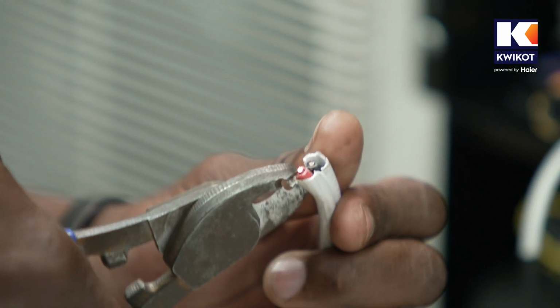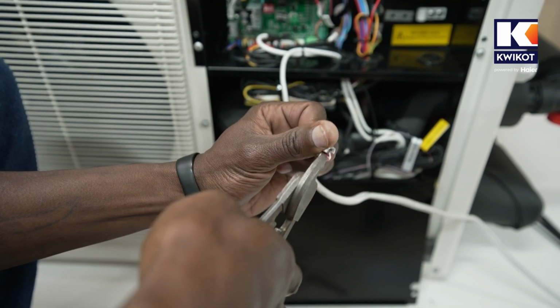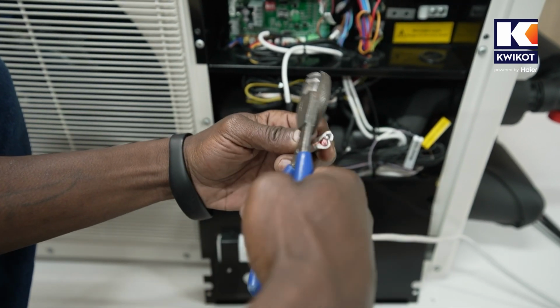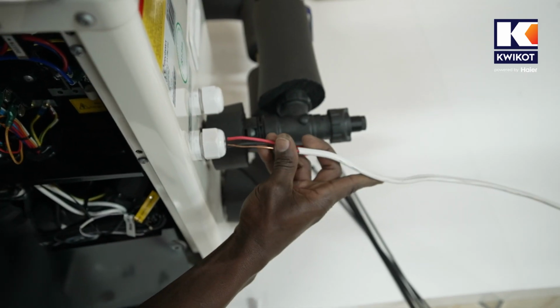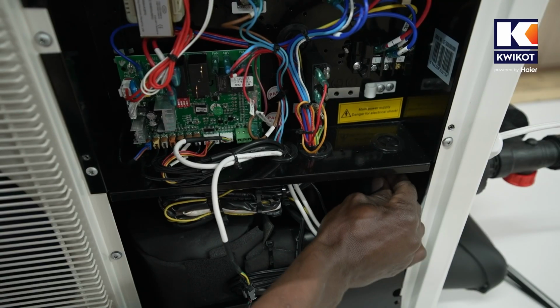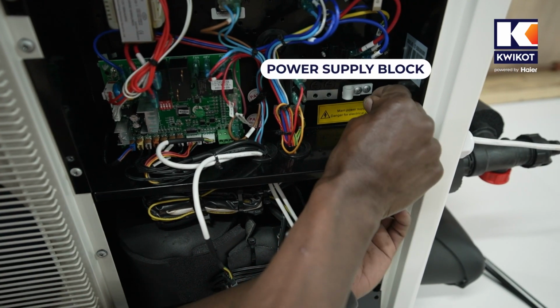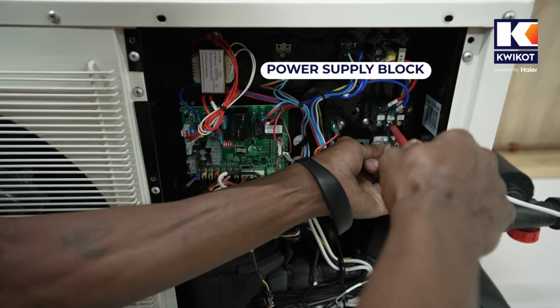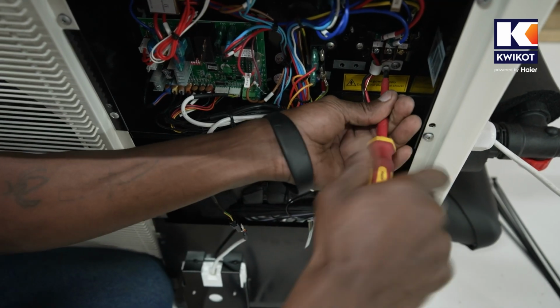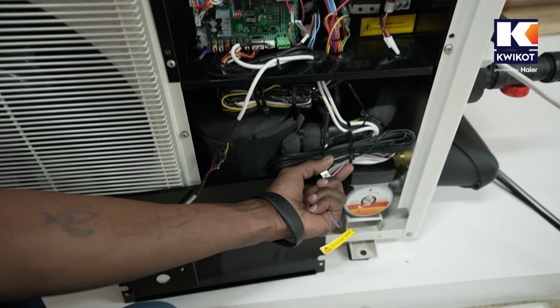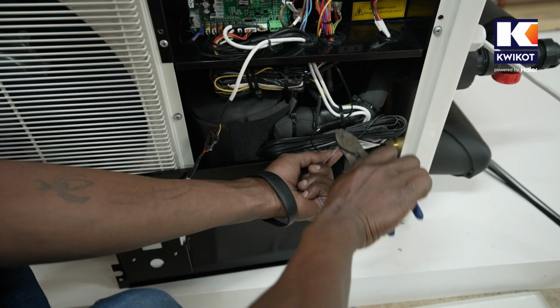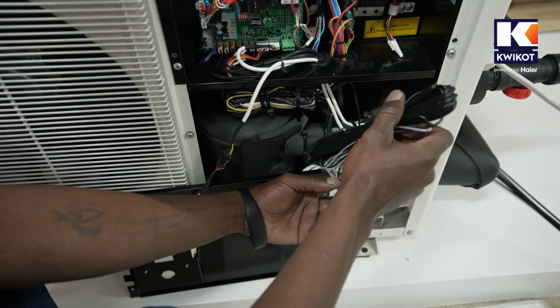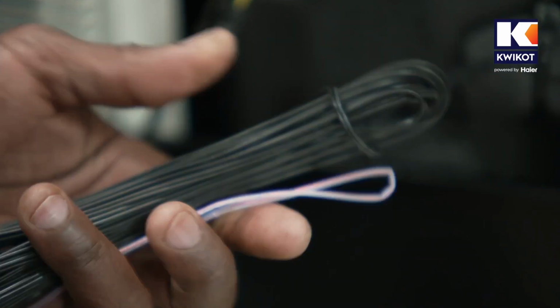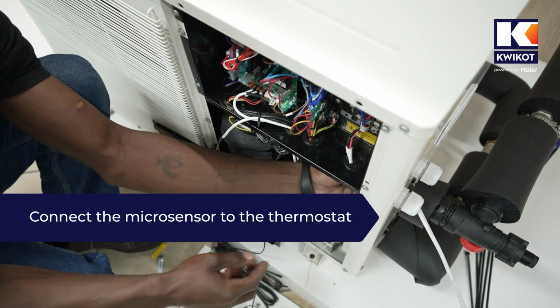First we're going to strip the end of the cable so that the live, neutral and earth wires can be separated. And then fit it to the correct ports on the power supply block on the right of the board. And then we secure the cable below the block. And next we cut the cable tie that is securing the microsensor cable, which is down here, and then pass it through the gland.